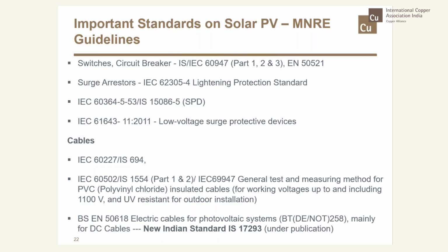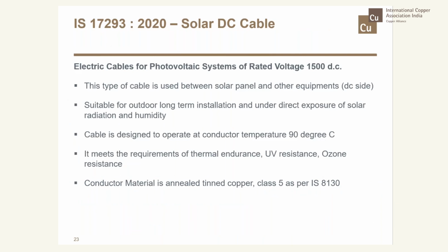These are all applicable. And as far as the DC side is concerned, the DC cable, for which so far an EN standard has been specified, but now a new Indian standard IS 17293 has been printed and is under publication. So anytime, in a week's time, it is going to come. IS 17293 is the solar DC cable. This is the electrical cable for photovoltaic systems of rated voltage 1500 volt DC. This type of cable is used between the solar panel and other equipment.